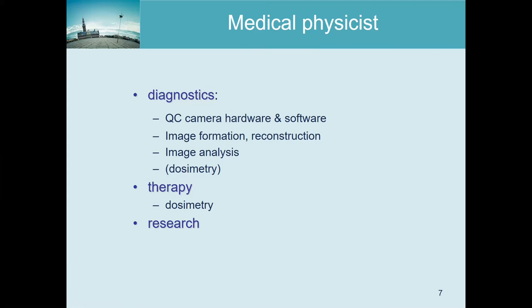So this course is intended for everyone interested in nuclear medicine, but in particular for medical physicists. And so what is their function if they work in a nuclear medicine division? One thing is to look after the cameras, the PET cameras, the gamma cameras, and all the other hardware. And the reason is that these machines are pretty sophisticated. They consist of a lot of components and the characteristics of these components can slowly change. So the quality of the images that they make can slowly degrade. And if you don't monitor that carefully, then the danger is that it will start affecting the diagnostic quality of the images.